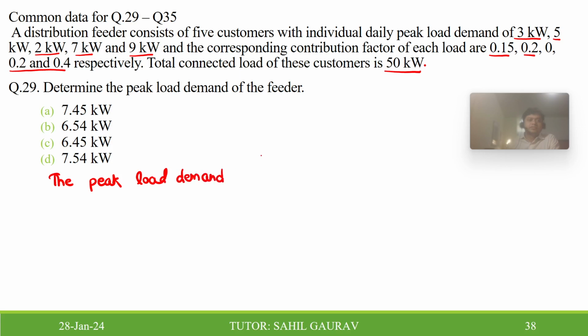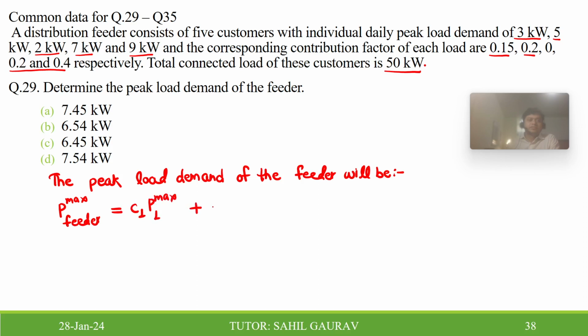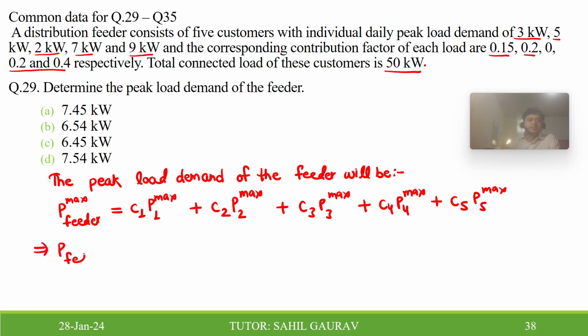When you are getting the answer, you can type your answer in the chat box. Peak load demand of the feeder will be: P feeder max is equal to C1, the contribution factor from customer 1, into P1 max, plus C2, the contribution factor of the second customer, and the individual peak demand of that customer, plus C3 into P3 max, the maximum demand of customer 3, plus C4 into P4 max, plus C5 P5 max. So put all these values.